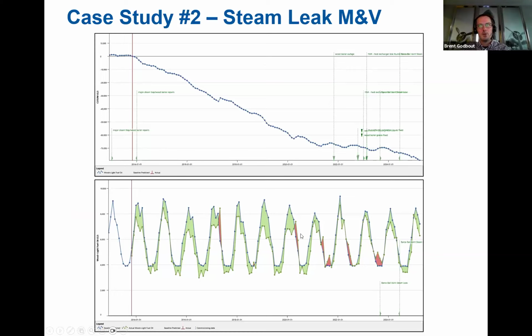Had a couple months here and there where we had some red. Then we hit this time frame where all of a sudden the expected use and our actual use are pretty much the same, so we're no longer saving that energy we had anticipated. Then finally, once we found all those steam leaks at those flanges and fixed them, we're back into the green again, and it's gotten even bigger. I should update this chart, but the slope's gotten even steeper as we've gone into the future.